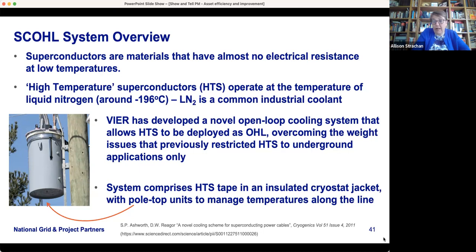Our project partners VIER have developed a novel open loop cooling system that allows high temperature superconductors to be deployed as overhead line. Cooling with liquid nitrogen in a closed loop system has significant weight issues, which restricted high temperature superconductors to underground cables only. This novel technology - there's a paper describing the science, really interesting if you want to read it - has an open loop cooling system which removes or reduces those issues. The system comprises HTS tape, the conductor, in an insulated jacket which provides the cooling.